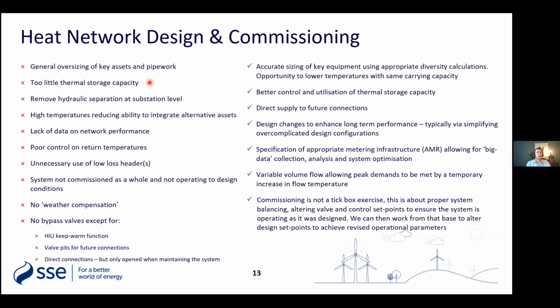Diversity, for people who don't understand, is basically when you're sizing equipment, you add up the peak demand for each apartment, each building, and then you apply a diversity factor that says that not all of those connections are going to be using their peak heating requirement at any one time. And people are still too conservative with those estimates.